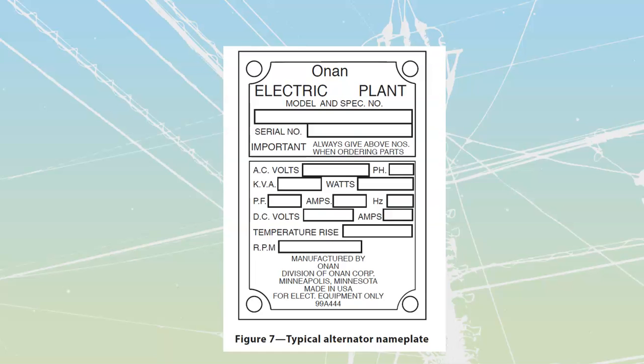You'll see ratings inside here that are not going to give you ratings in kilowatts. They're always going to give us kVA, because we have no idea what our customer is going to hook up to that, or what the power factor will be. If we don't know what the power factor is, we don't know what the actual kilowatts are going to be. We always give everything off the kVA capabilities.